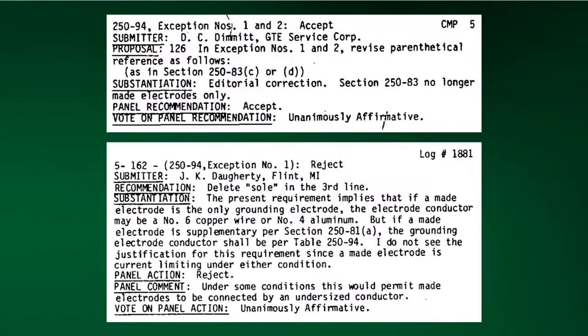Then they come down and they talked about the, so in the 3rd line, it says the present requirement implies that if a made electrode is the only grounding electrode, the electrode conductor may be a number 6 wire, number 4 aluminum. But if a made electrode is supplementary per 250.81A, the grounding electrode shall be per table 250-94. Now, this is where a problem is, because they're trying to say that I can size to a supplementary based on the table. And it says, I do not see the justification for requirement since a made electrode is current limiting under either condition. And then they rejected it.